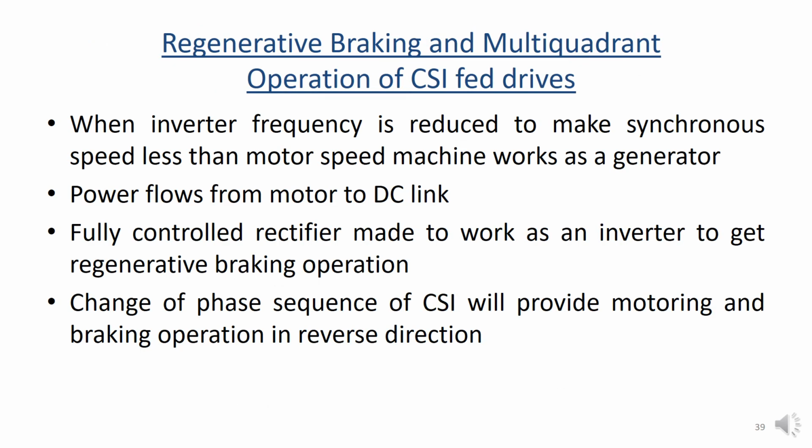Now let us see the regenerative braking and multi-quadrant operation of CSI drives. When the inverter frequency is reduced to make the synchronous speed less than the motor speed, the machine works as a generator. The power flows from the motor to the DC link. The fully controlled rectifier is made to work as an inverter to get regenerative braking operation. The change of phase sequence of the CSI will provide motoring and braking operation in the reverse direction.